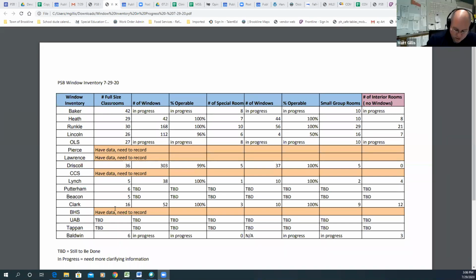Carlos, could I trouble you to repeat that calculation? Natural ventilation: you want the window opening to be 4% of the floor area of the space. That's based on natural ventilation, but it would help the ventilation of the building even with mechanical ventilation, such as unit ventilators.